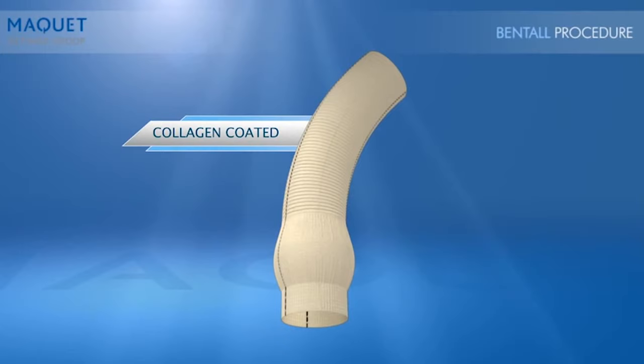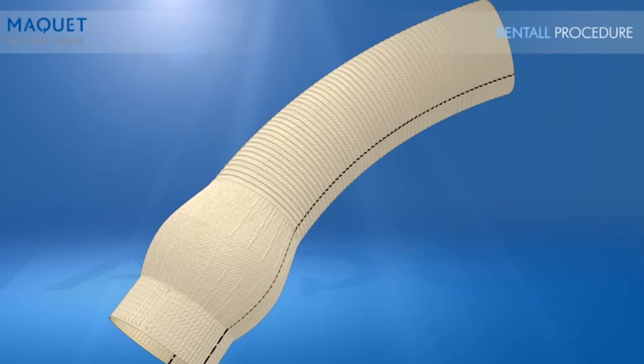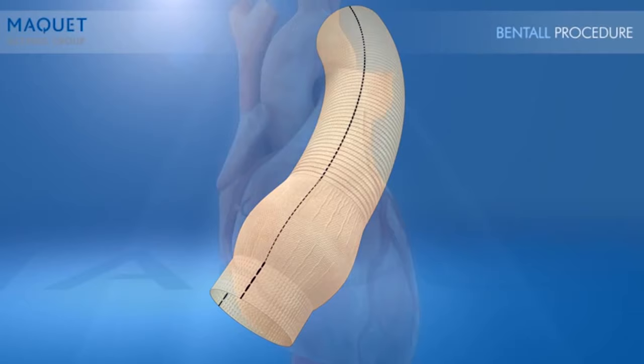The Maquet CardioRoute is a collagen-coated one-piece device designed to repair or replace the ascending aorta. The CardioRoot graft features three distinct sections in one piece, unlike other grafts that are three pieces sewn together. The three sections are the body, the bulge, and the collar. The bulge was specially designed with a smooth surface and distinctive shape, mimicking the anatomy of the native aortic root and coronary sinuses.